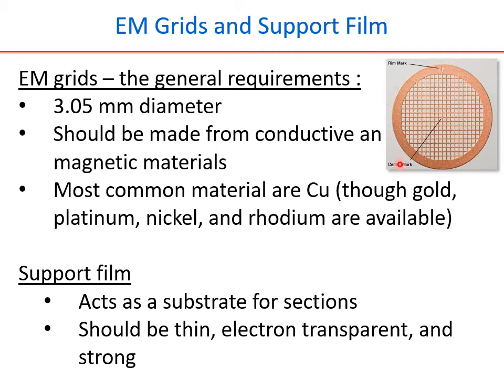If you keep a magnetic material here, it may influence the magnetic field at the condenser lens and the objective lens, and thereby it can cause a malfunction of the instrument or slight misalignment of the instrument. So in order to avoid that, it should be a non-magnetic material. This is a misnomer here. Just read this as a non-magnetic material. So this is the whole idea. It should be a conductive and non-magnetic material.